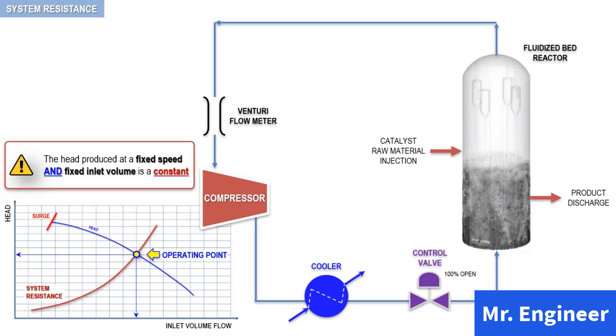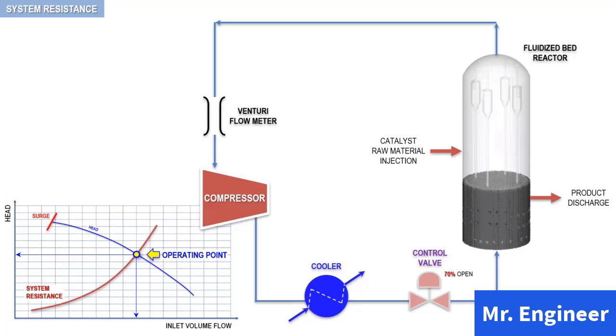An important point to remember is that the system resistance curve can change and will certainly do. For example, throttling the discharge valve to 70% will increase the system resistance, which will result in a steeper curve, as highlighted here.